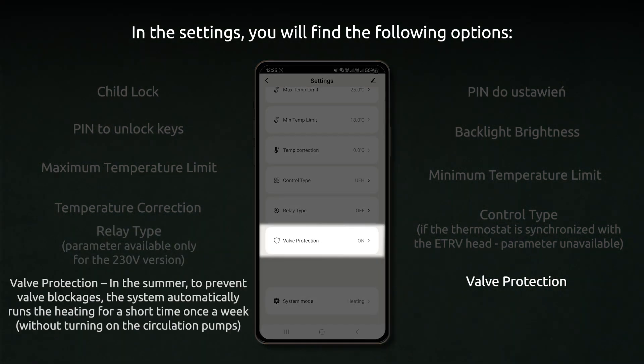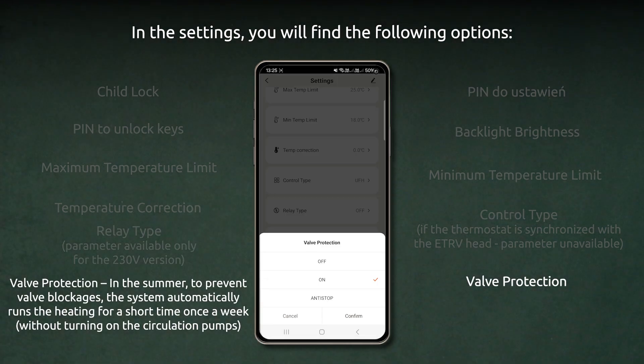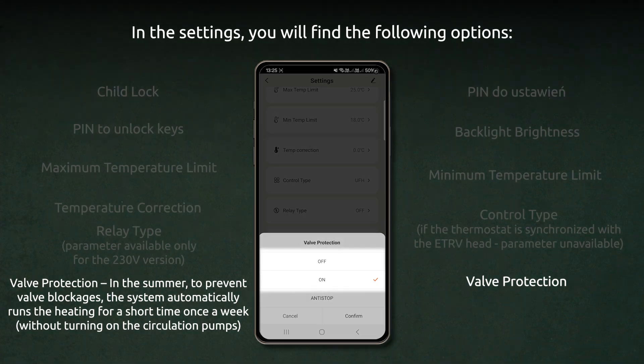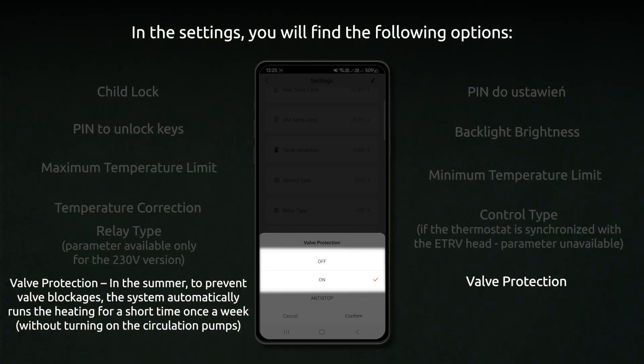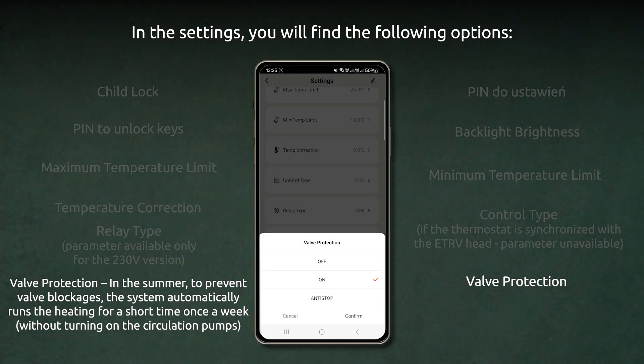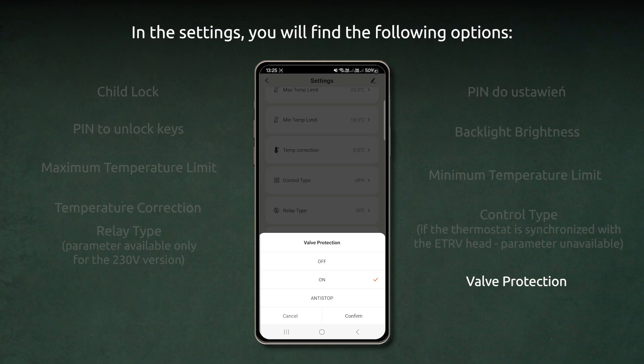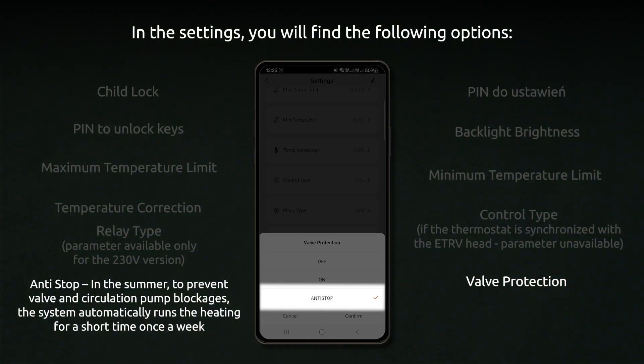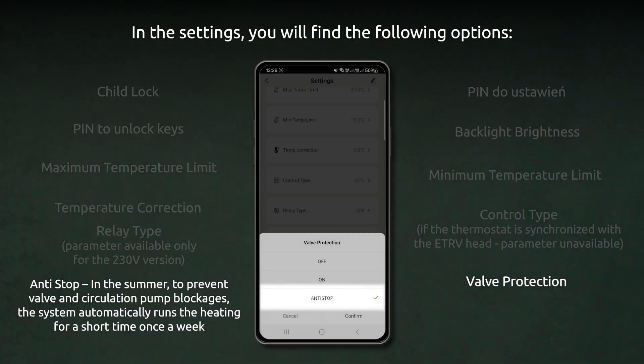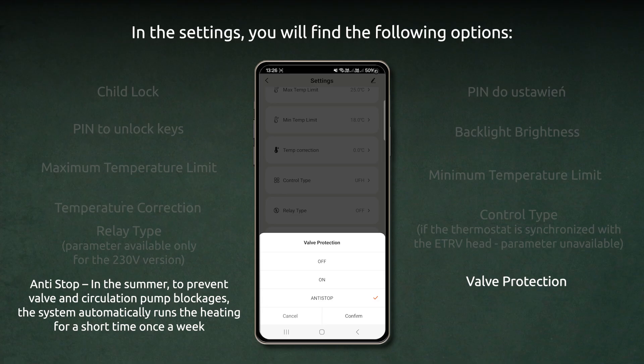Valve protection. In the summer, to prevent valve blockages, the system automatically runs the heating for a short time once a week, without turning on the circulation pumps. Anti-stop. In the summer, to prevent valve and circulation pump blockages, the system automatically runs the heating for a short time once a week.